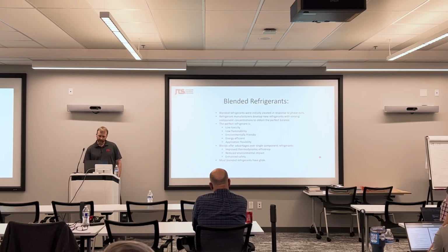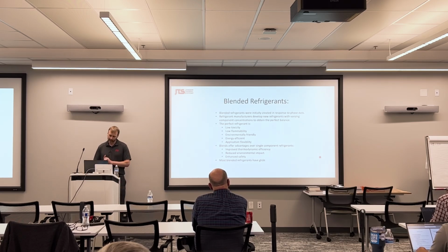All right, so blended refrigerants were initially created in response to phase-outs. Refrigerant manufacturers develop new refrigerants with varying component concentrations to obtain the perfect balance. The perfect refrigerant has low toxicity, low flammability, is environmentally friendly, energy efficient, and has great application flexibility. Blends offer advantages over single component refrigerants in the sense that you can get improved thermodynamic efficiency, they reduce the environmental impact, and enhance safety. Most blended refrigerants have glide.